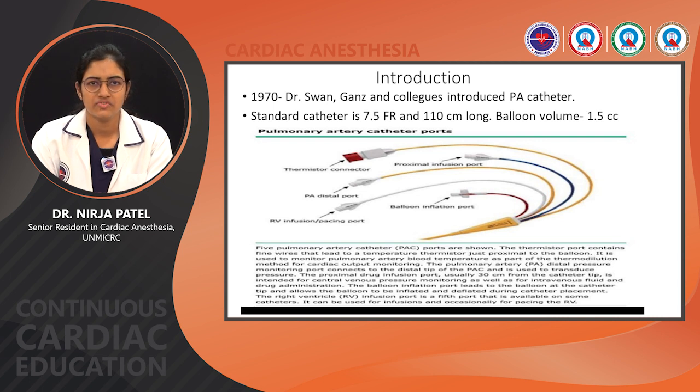As you can see in this figure, it has many ports. One is for balloon inflation, another is the proximal infusion port, the distal infusion port, one port is for pacing catheter insertion, like the pacing port, and one is for the thermistor connector.